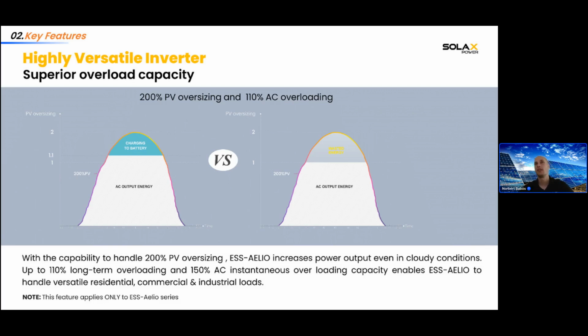I think the most advanced key feature is the oversizing of the PV, because it can support 200% of PV oversizing with the AELIO. That means if you have a 50 kilowatt inverter connected, and you connect 100 kilowatt of PV panels, you can charge the batteries, just like here in the first picture. The first limit would be to supply the loads that you need with 50 kilowatt of power, but then with the 110% oversizing of the AC, you can supply the loads with 55 kilowatt, and then with the rest of the 50, you can charge the battery.